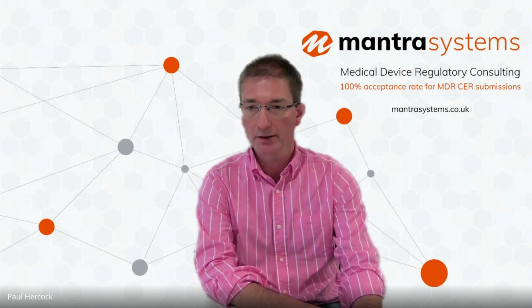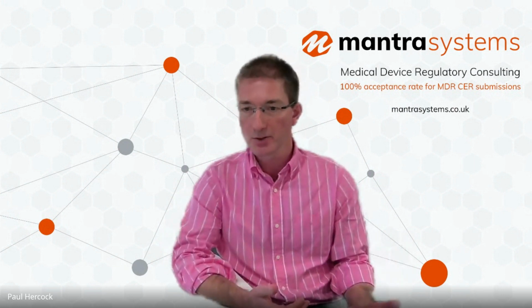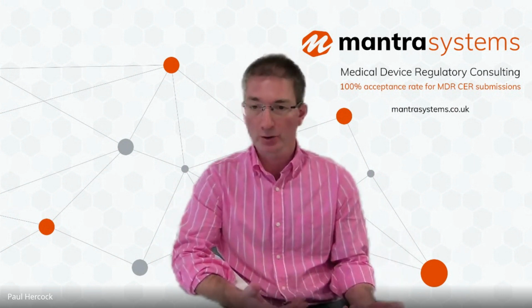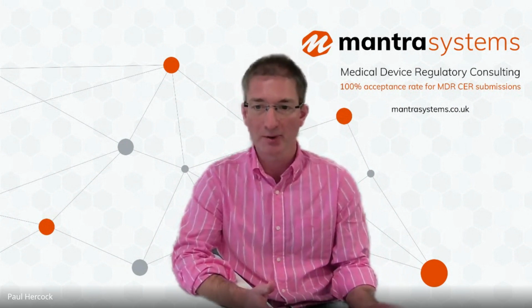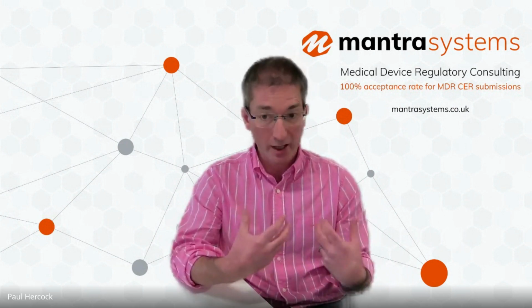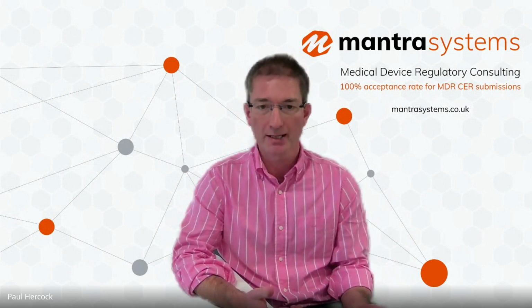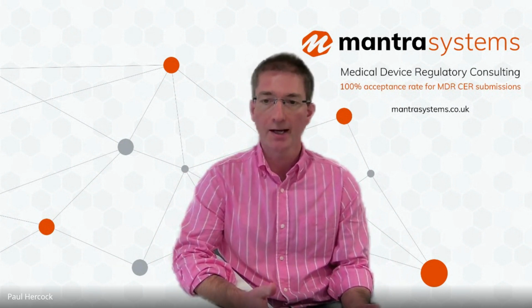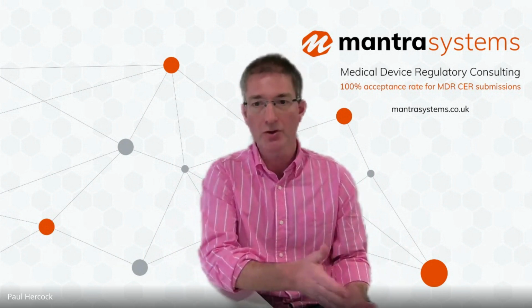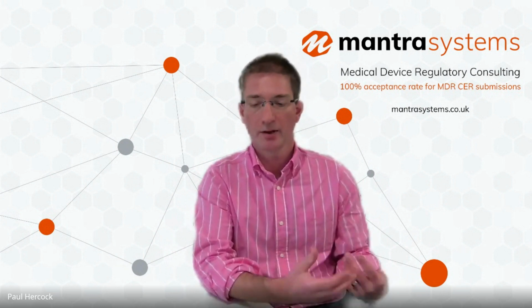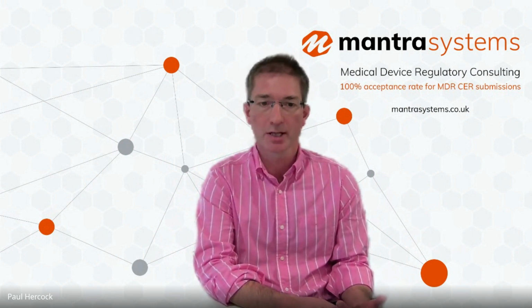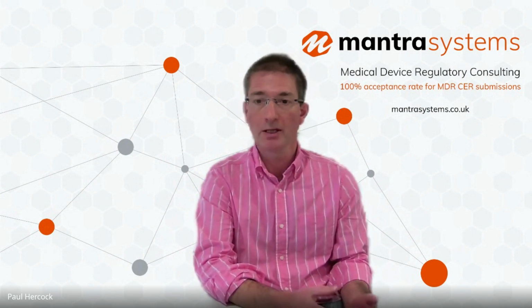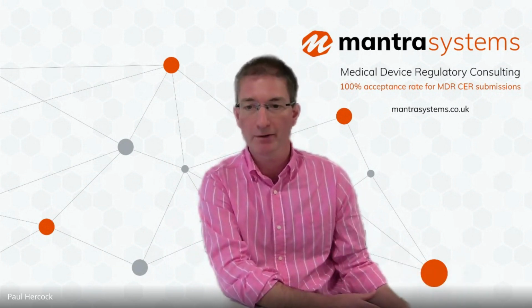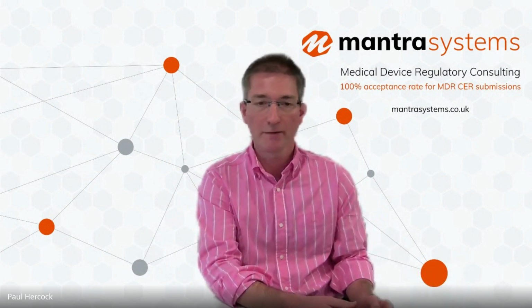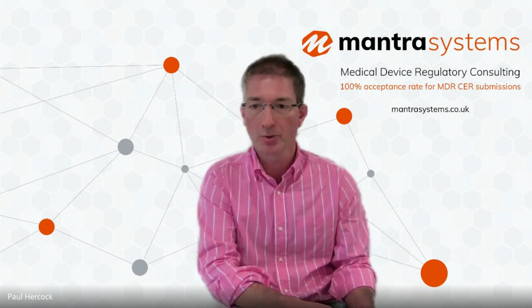It goes back to basic principles of doing a clinical evaluation. The first golden rule, which we always adhere to, is it's a much bigger job than you think. So you're going to need a team of people if you have a tight deadline to do this properly. And the reason for that is that it's going to be necessary to run several different streams of work in parallel. The piece which normally takes the most time is the state-of-the-art literature review. I say normally because sometimes there are comparatively few relevant sources, but that's the exception. Oftentimes, this is where you'll need the largest number of people and need to spend the greatest amount of time.